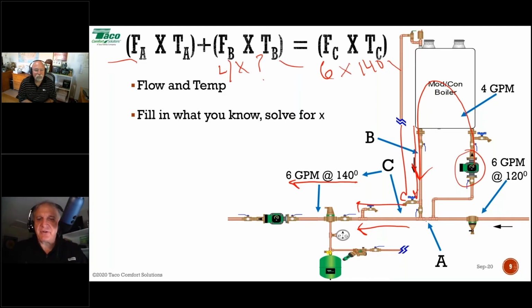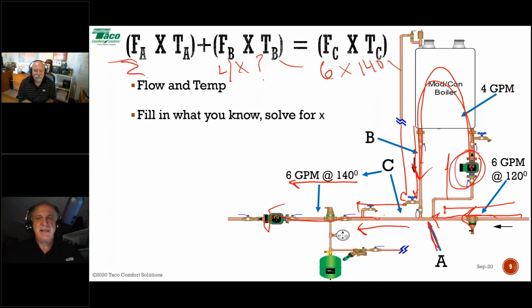Now we got to figure out the flow and temperature here. So think about this for a minute. If I've got 6 gallons a minute at 140 going out to the system, and I'm operating on a 20-degree delta T in this example, I have to have 6 gallons a minute coming back, don't I? And it's 20 degrees less, so 6 gallons a minute at 120. 6 gallons a minute at 120 enters this T. This pump is on. The boiler needs 4 gallons a minute. So my flow rate through A is going to be 6 gallons minus 4. What am I left with here? That's going to be 2 gallons a minute. And what's the temperature going to be? Well, it has to be 120, right?